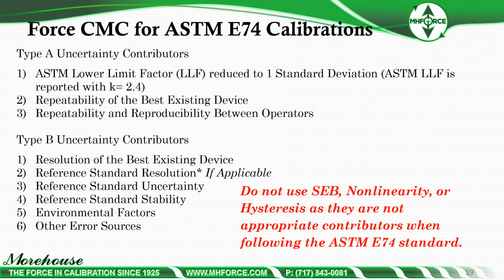So when we talk about those uncertainties, we talk about what goes into that. If you're familiar with type A and type B uncertainty contributors, the type A contributors for these type of calibrations typically are ASTM lower limit factor. That's reduced to one standard deviation.